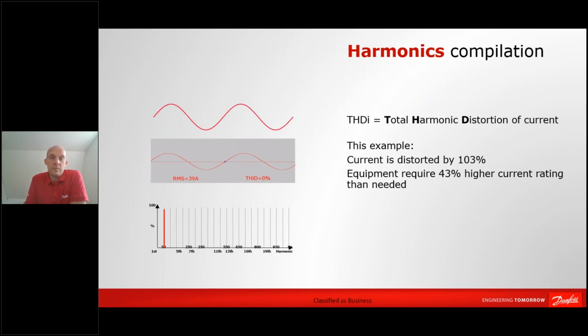Normally we do that with the help of Fourier analysis or fast Fourier transformations. And what we basically do is we're trying to represent the distorted current waveform by a sum of sinusoidal waveforms. There was this French mathematician that found out that you can represent any given signal in terms of sinusoidal waveforms as long as they are repetitive and continuous. And if you had a signal like we had before, you can actually represent that not by one current waveform, but by a sum of sinusoidal waveforms. So that is actually what I'll try to do now. I'll try to generate the current waveform you saw before by adding sinusoidal waveforms together.